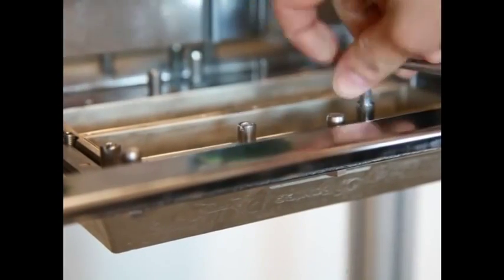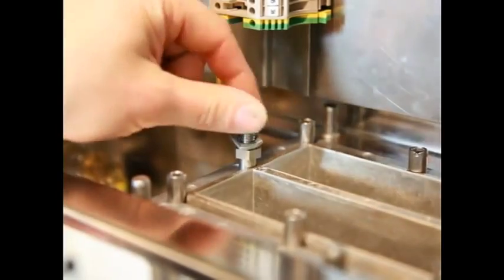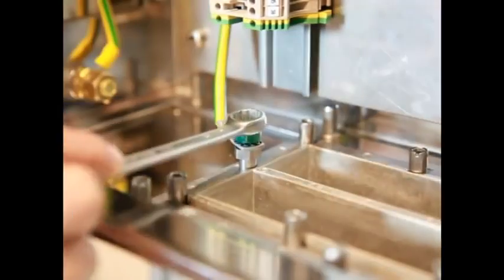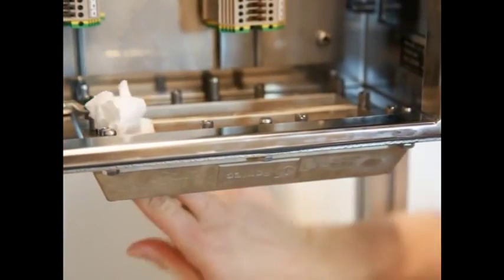Tighten the nuts and secure the ground lug to the lug of the enclosure. Clean the frame, removing paint and dirt to ensure good electrical conductivity.